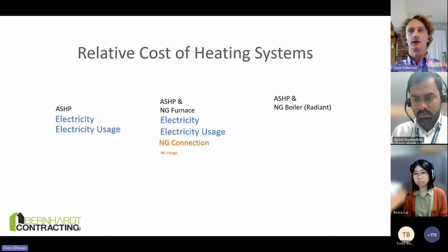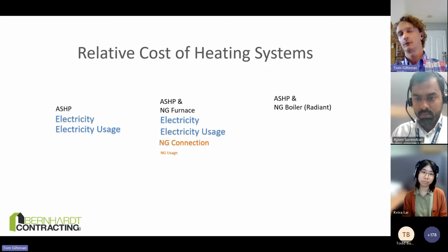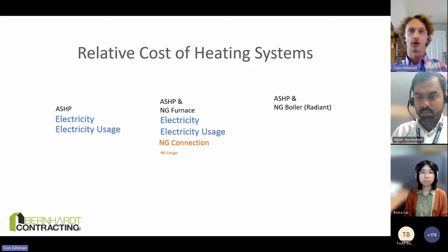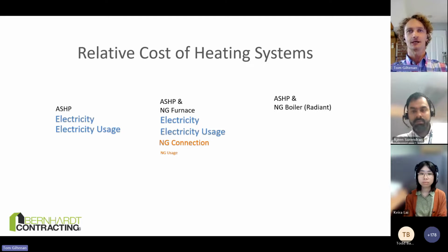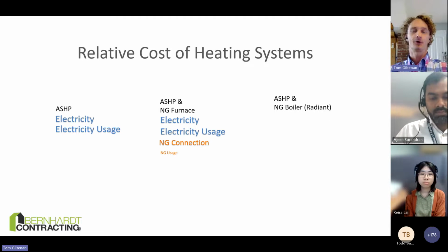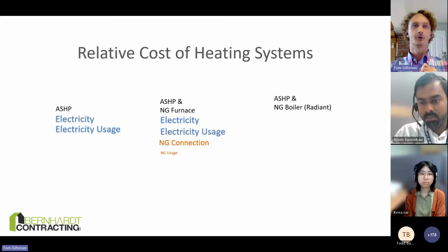And then if we look at a heat pump with a boiler, and this is specifically with radiant heat, I'm bringing this up because radiant heat, as we begin to build higher performance buildings, is less and less useful. It comes on so infrequently that you will not get your warm floor feeling, your warm feet. You will not have that, in the lower mainland, almost 100% of the time.